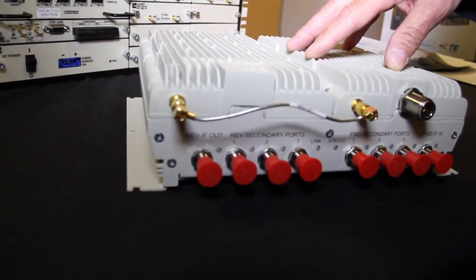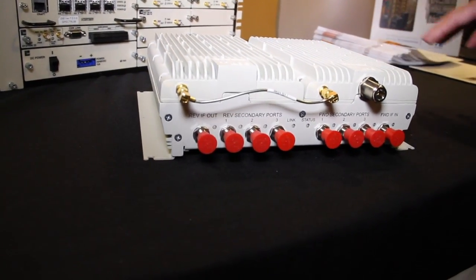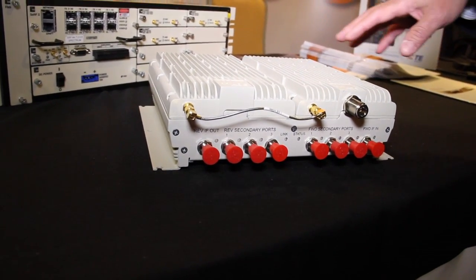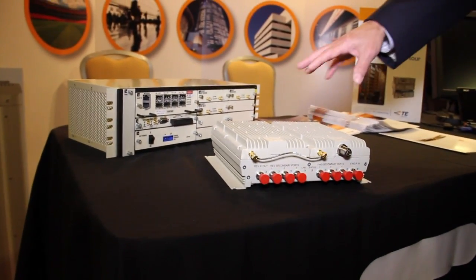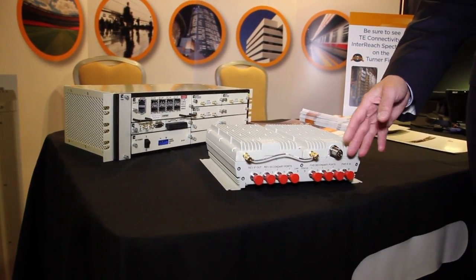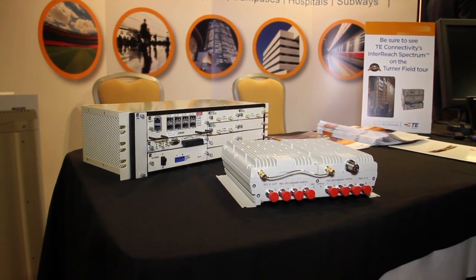This is a main remote access unit that would support 850 and 1900, and then could support an additional three remote access units that would support up to eight total bands at a single antenna location. The advantages are the full power output at each antenna location, zero loss system, feeding over standard building cabling techniques such as CATV 75-ohm cable TV cabling, and then the digital advantage of having a 26 dB budget for the digitized fiber RF on that end.